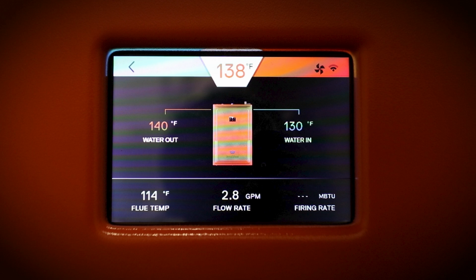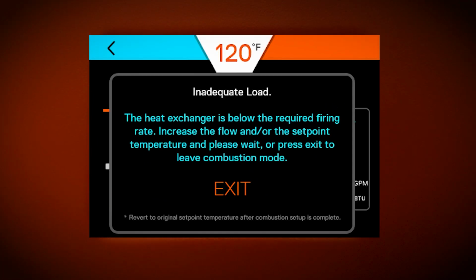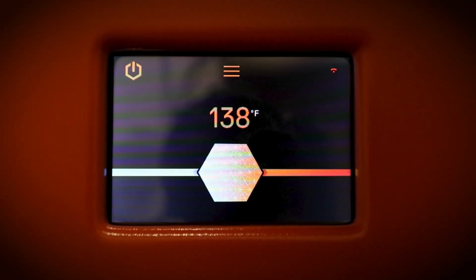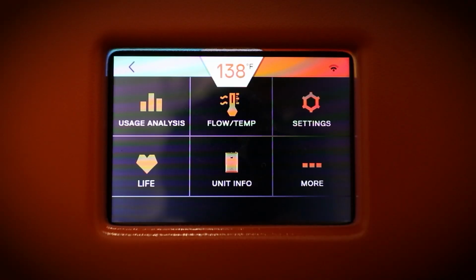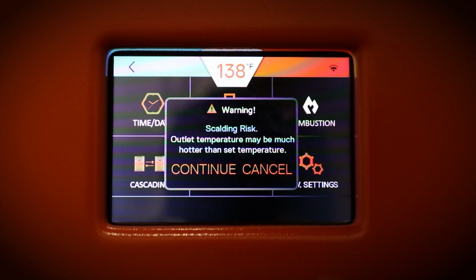If this value is less than 250,000 BTU per hour, create more demand by increasing the flow and/or increasing the set temperature. Note that if the hot water is currently in use or if there is a mixing valve installed, increasing the set point temperature may not be possible. If you do increase the set point during combustion, remember to change it back to its original setting after you are finished. Next, on the display, navigate to Menu, Settings, Combustion.